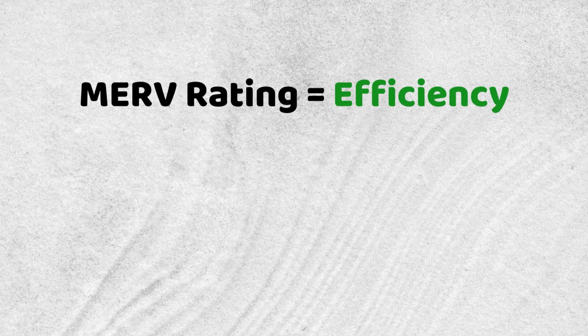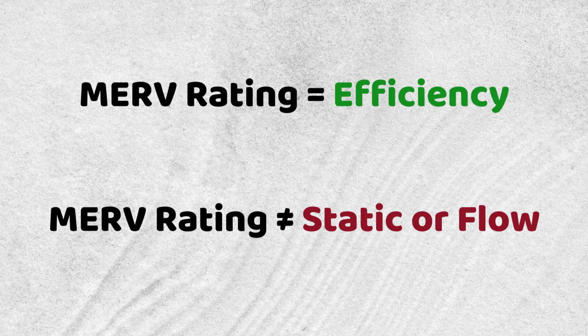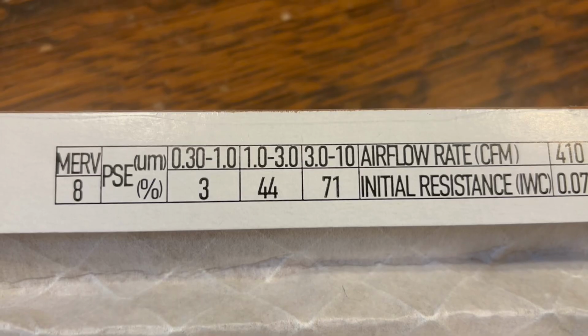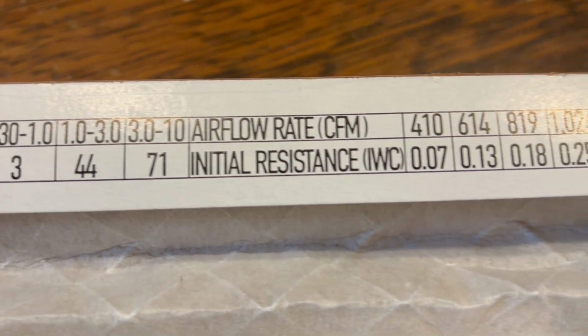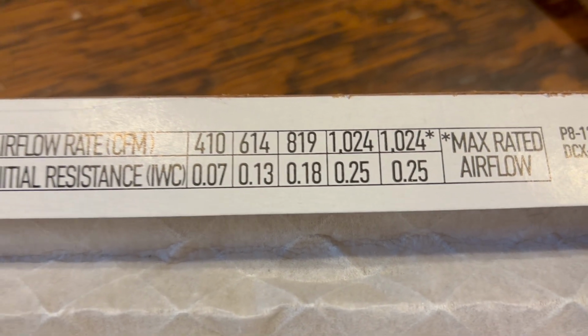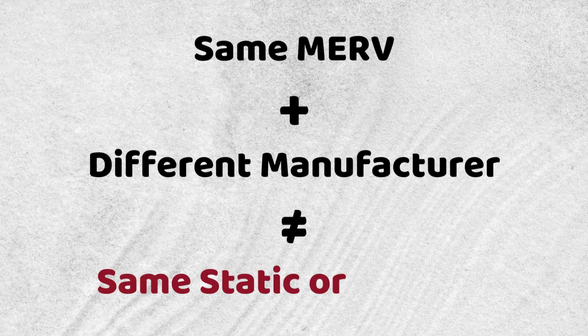A lot of the systems now have thicker filters, thicker than these 1-inch ones, so you're getting more surface area, allowing more air to flow through while still capturing the debris. But ultimately, I think it's worth taking some readings and really checking out what filter is going to work best for your system. And also know that MERV ratings are not standardized to correlate with a specific pressure drop, static pressure, or airflow. There's definitely variation that can be found amongst filters of the same MERV rating from different manufacturers. So just something to keep in mind as you're choosing filters. One MERV 8 is not always going to be the same as another MERV 8.